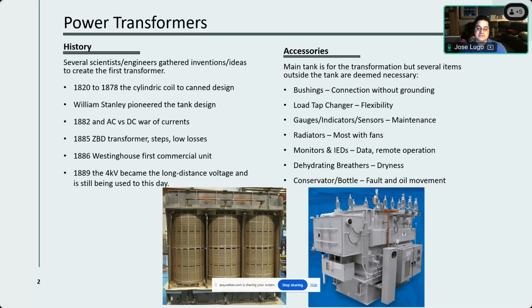The radiators are meant to cool down a power transformer by having oil flow to the top, which is usually where the hottest oil is. Transformers are filled with oil for dielectric reasons, and the radiators let it flow down. You can put fans on those radiators, which is another accessory—most radiators have fans, because with fans you cool down the oil a lot better.